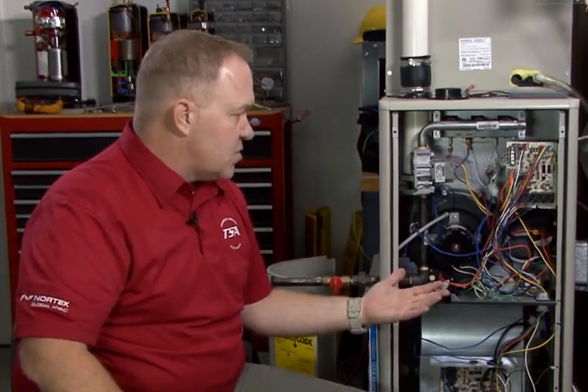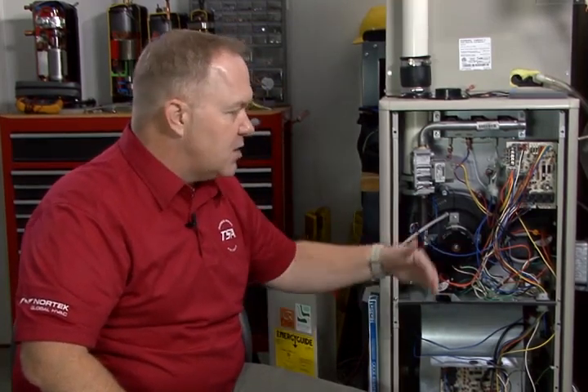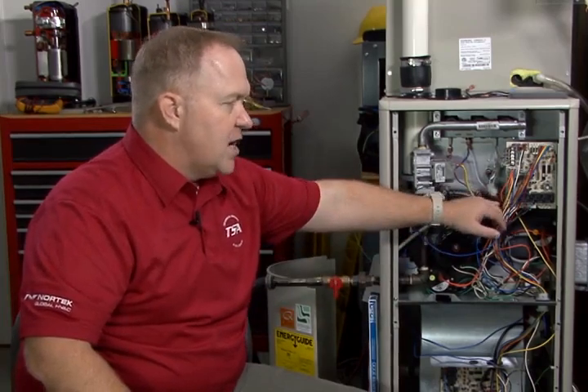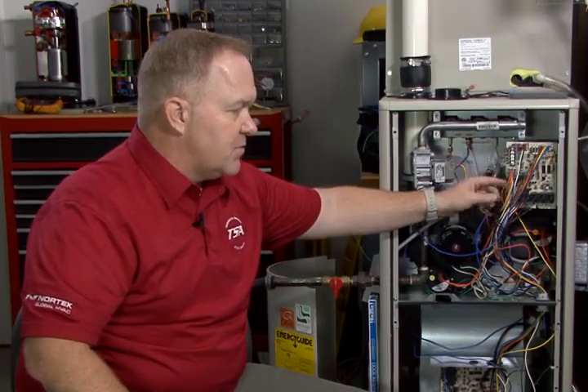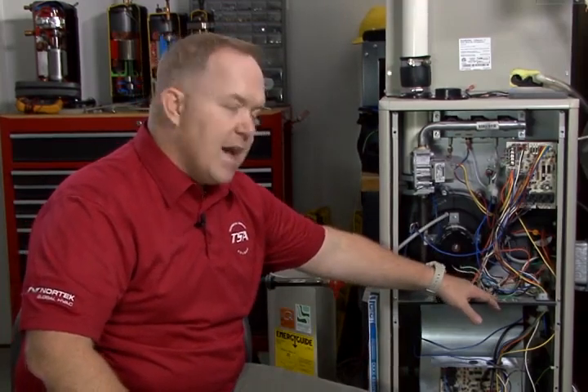If you want to test ground, you can do that very quickly, very easily when the power is on to the furnace. If you test from the incoming neutral from the panel for the furnace, from neutral to ground, you should read no AC volts whatsoever. If you begin to pick up AC volts from neutral to ground, that can indicate that you don't have a significant earth ground in that circuit. If you read anything greater than half a volt AC from neutral to ground, that will definitely indicate that you do not have a substantial earth ground reference for that circuit that's providing that furnace with power.